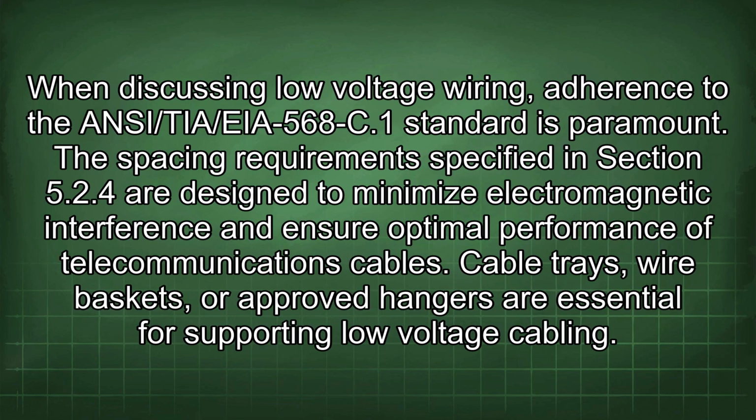When discussing low-voltage wiring, adherence to the ANSI/TIA/EIA-568-C.1 standard is paramount. The spacing requirements specified in Section 5.2.4 are designed to minimize electromagnetic interference and ensure optimal performance of telecommunications cables. Cable trays, wire baskets, or approved hangers are essential for supporting low-voltage cabling.